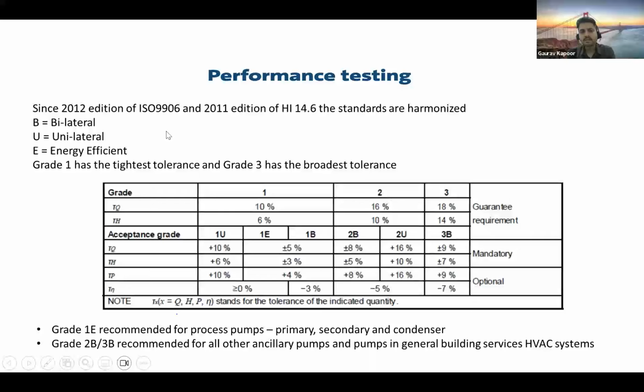You should always get the data sheets from the manufacturers based on any one of these standards, and they should clearly mention whether they are giving you 3B, 2U, 2B, 1B, 1E, 1U, the acceptance grades which are mentioned here. And if you look at the bottom columns, these are different grades available. So TQ means tolerance for flow, TH tolerance for head, TP tolerance for power, and T eta is tolerance for efficiency. So these are the tolerances which are allowed within these testing standards.